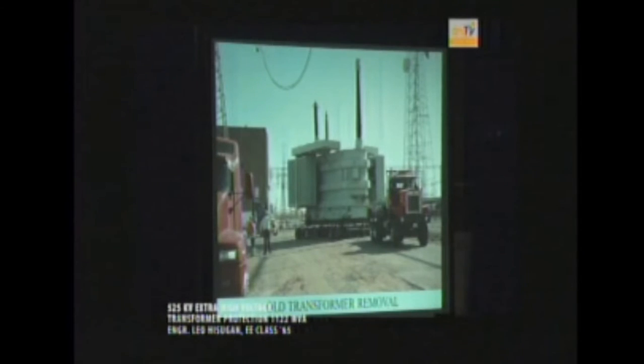Like 5 years ago, we had the opportunity to change some of our old units with the brand new one. And this is the picture of the old 525 kV transformer installed in 1967. Next is our transformer being removed in the foundation. We're using some big concrete breakers now to remove the old foundation. And now this is the brand new transformer foundation. This is normally your metal foundation here, metal support for your foundation.